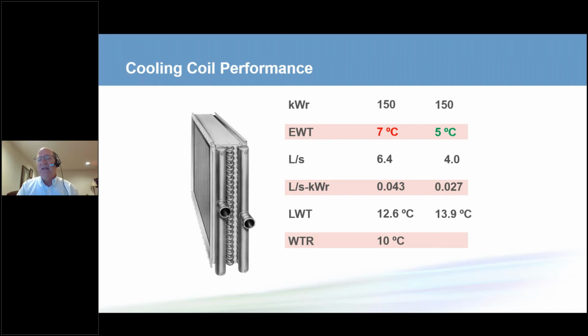The leaving water temperature, when we look at how heat transfer works with that log mean temperature difference, when we reduce the inlet temperature to that coil, the outlet temperature will also go down because of how heat transfer works. Therefore, we can go from a 6-degree C delta T to a 9-degree C delta T. Pardon me, this is degrees F on the slide, I didn't get this right, and I'll correct that slide before I send it to Money to be posted on the chapter website. So the delta T goes up, but again, the chiller has to provide colder chilled water temperature.